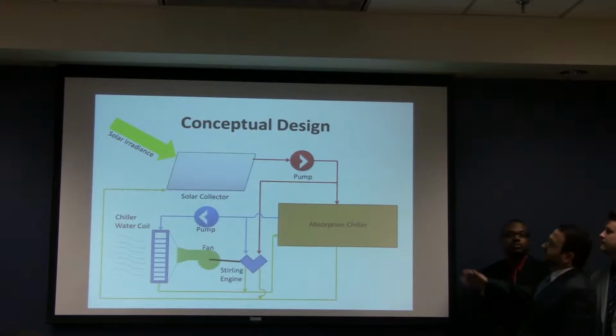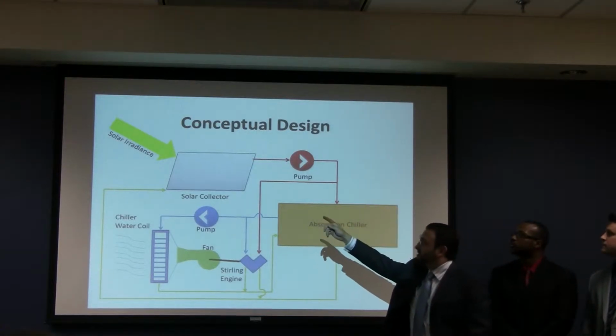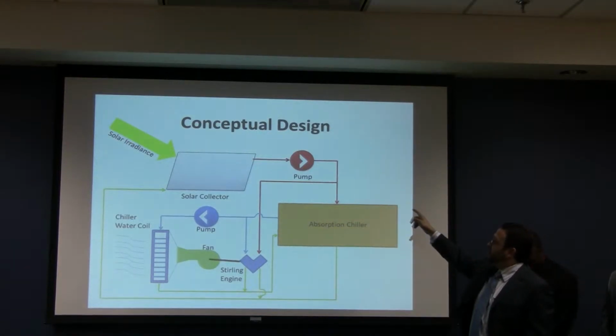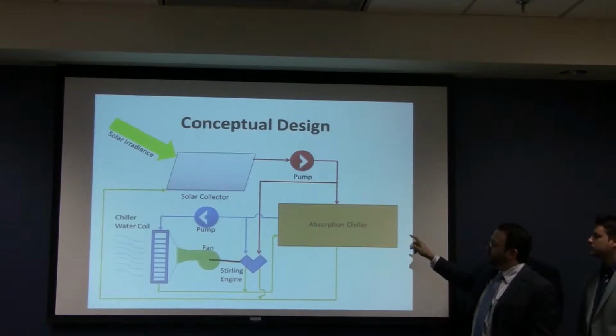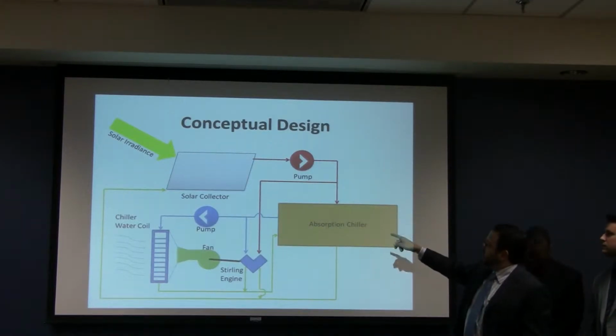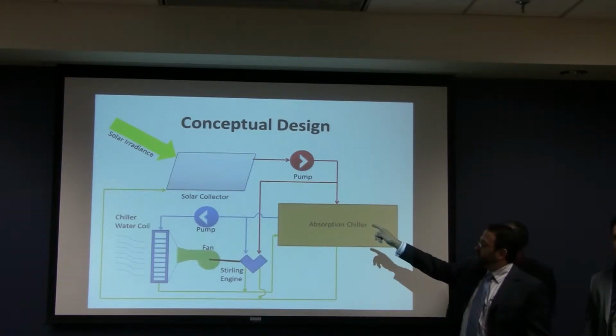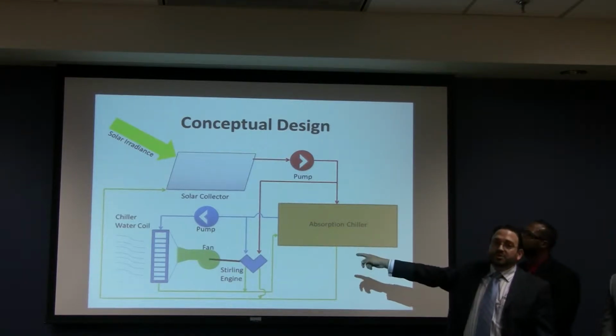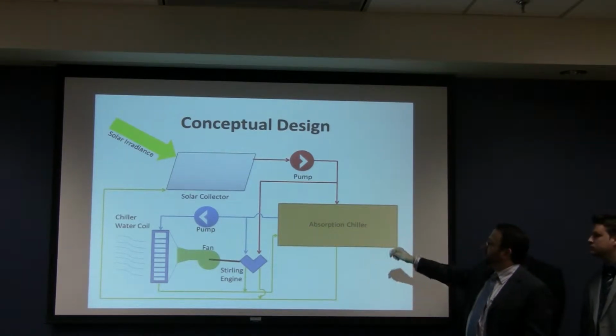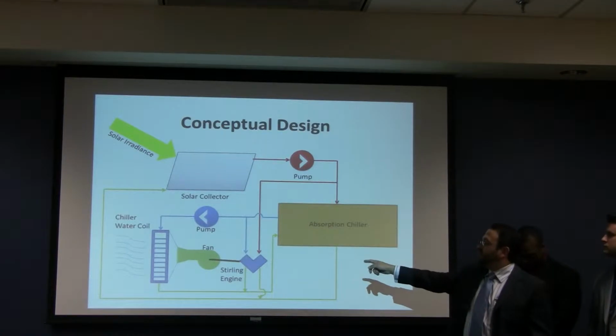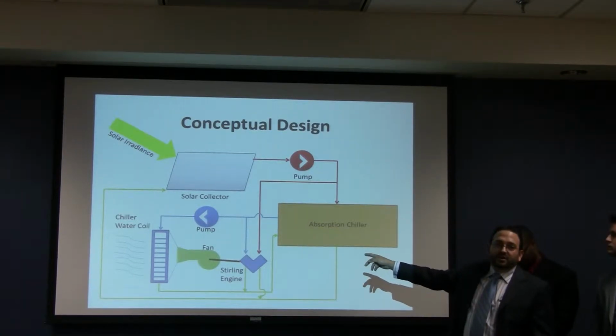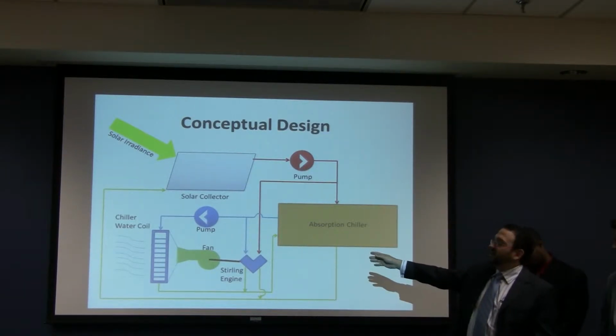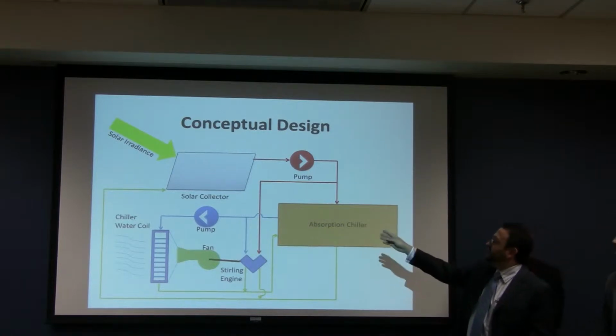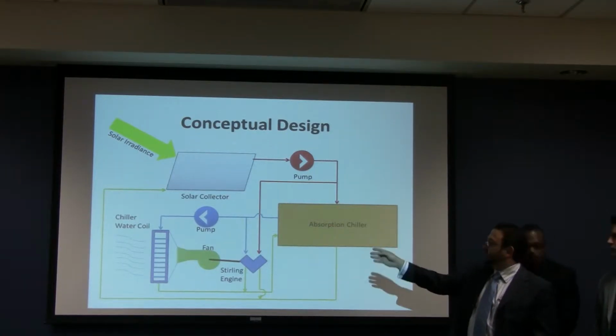The conceptual design is to use a solar collector to collect the solar irradiance, and pump that hot water into the absorption chiller and back to the solar collector. The absorption chiller would pump chilled water out to a chilled water coil with a supply fan and back to the chiller. The supply fan will be powered by a Stirling engine, which is also a thermal design, not electrical. So the entire system is all thermomechanical, not using electricity.